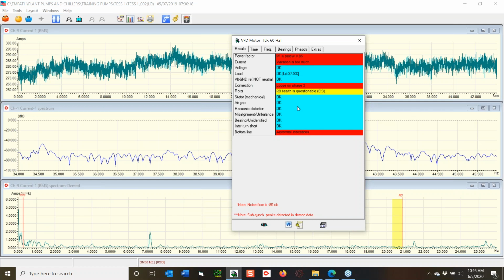And I'm all set. So just so happened on this one, we selected the right cable because we had 3 cables in a row. When I'm actually looking for loose connections where I have multiple cables, I'll use a Rogowski coil around them. So I have this now. I'm going to show you the report first, then we're going to go in and look at data. So let's go ahead and just have it generate a report. It takes a few minutes, but it will show me the summary of everything we just looked at there. It also has some screen captures in the back.